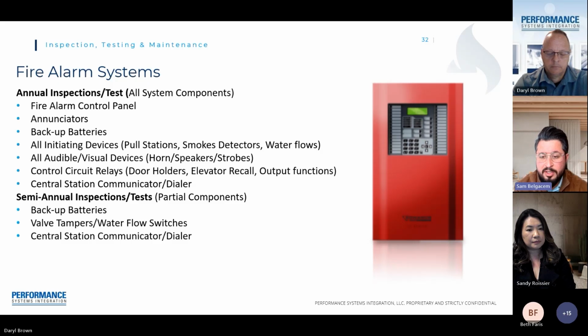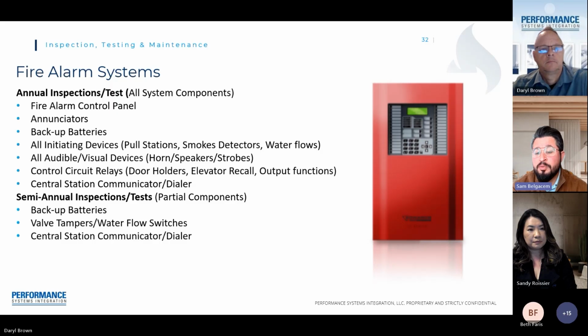The annual inspection is a little bit more involved. We basically check the system and test it as if there is a fire going on. So for instance, we introduce smoke to the smoke detector and make sure that the smoke detector works and sends the signal to the fire panel, and that triggers the alarm. We pull a station, for example. We pull the station and make sure that once we do the action of pulling the station, it will send the signal to the fire alarm, and then it will trigger the alarm.